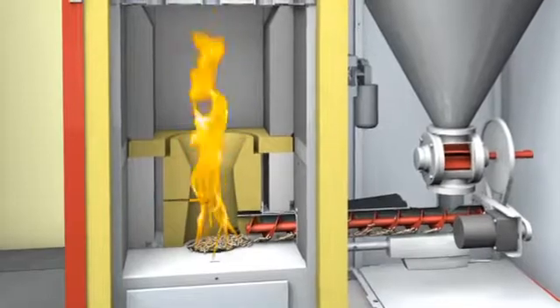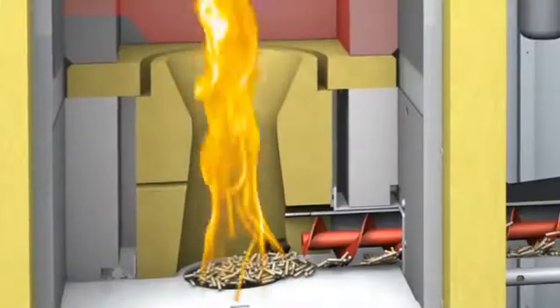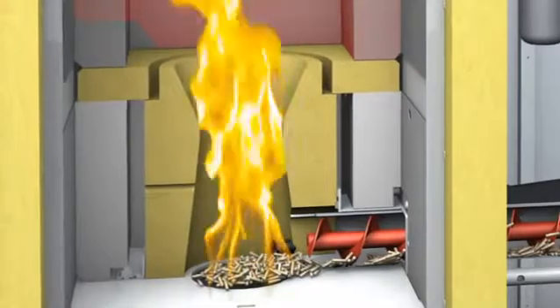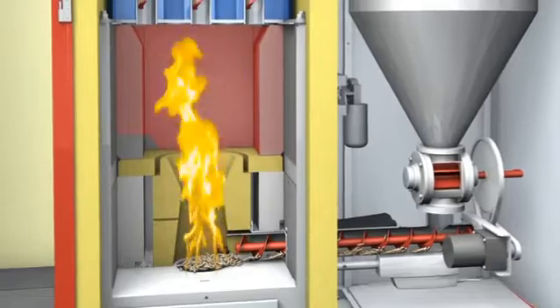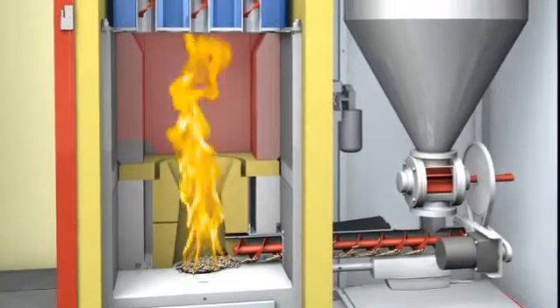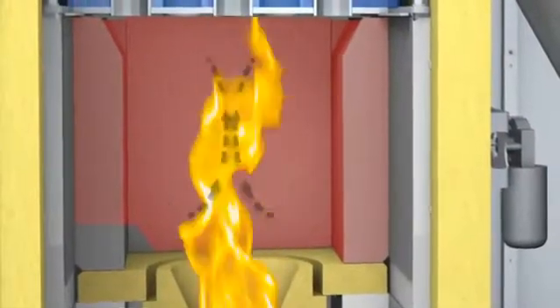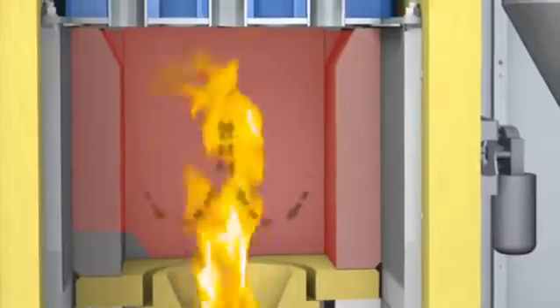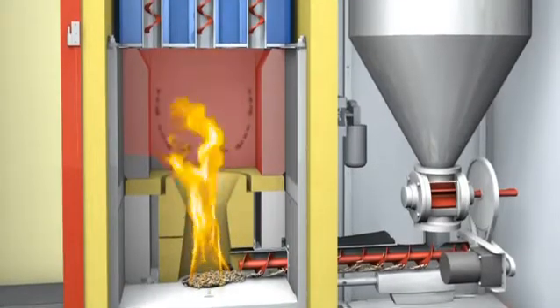Refractory has proved to be the most suitable material in regard to heat retention, durability and functionality. The high burning temperatures, in excess of 1000 degrees at full and partial working conditions, contribute to the high efficiency and the very low emissions. An optimized high temperature circulation zone carries the particles which escape from the combustion chamber back into the gas stream, thereby ensuring complete combustion.